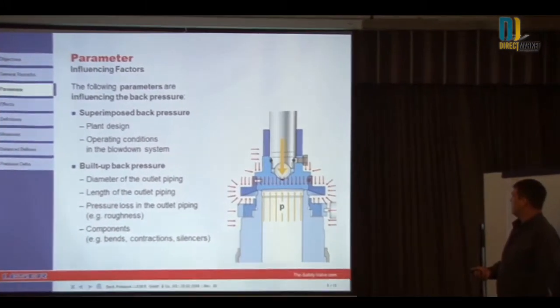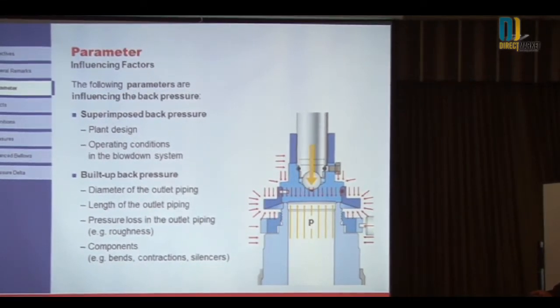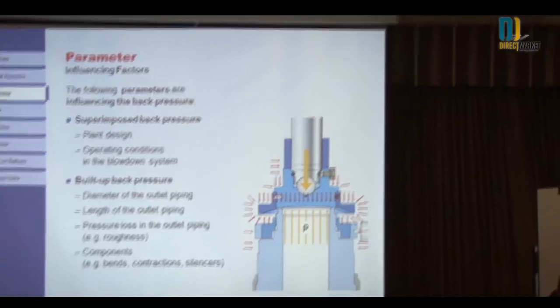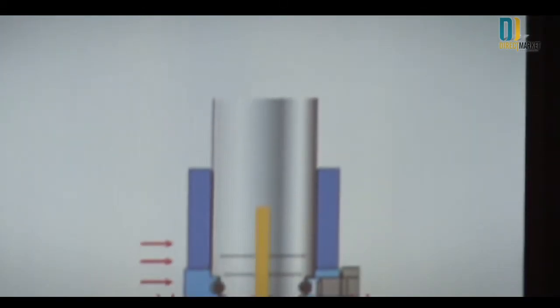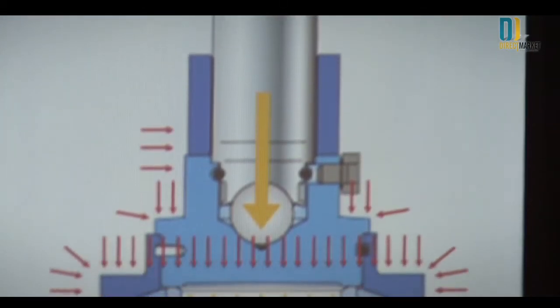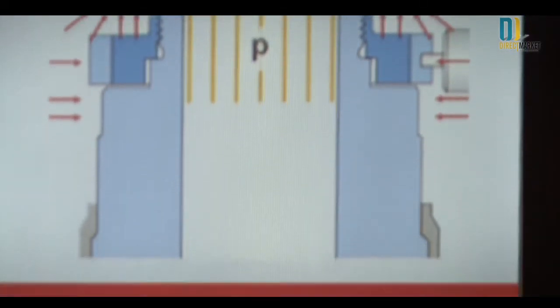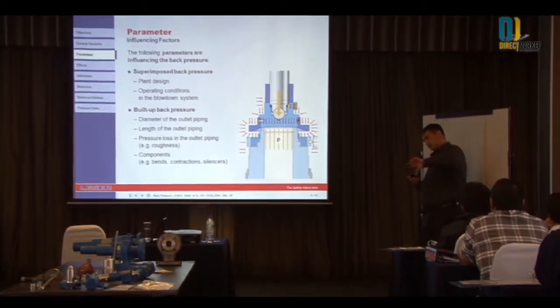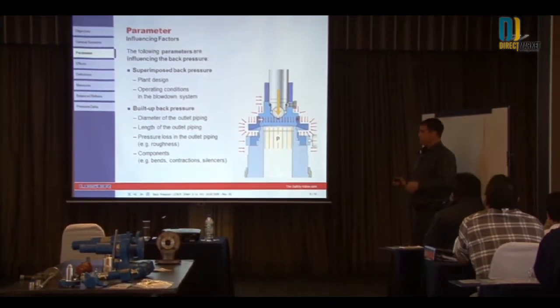Some of the reasons there's superimposed back pressure are plant design and operating conditions in the blowdown system. Built-up back pressure influencing factors include the diameter of the outlet piping, the length of the outlet piping, pressure loss, and friction through your system when the valve goes off and tries to relieve.